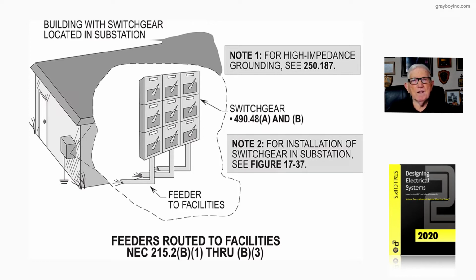The switchgear, 490.48 A and B would give you the instructions how to service it with components. In this case, you know, we have circuit breakers. So you'd look at 490.21A for that arrangement. Then notice the conductors in the raceway, you'd have to go over to the new Article 311, and you would pick a table out that listed these conductors in an underground run and what the ampacity of each one of those conductors would be based upon their insulation and say 90 or 180 degree C temperature.